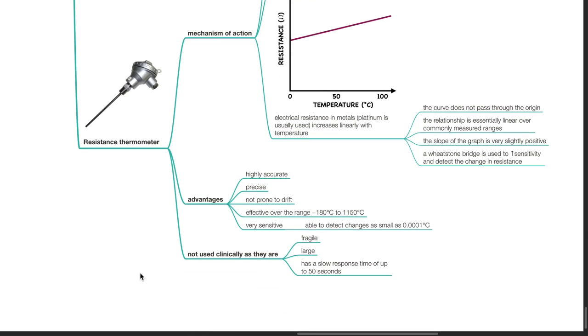Advantages of resistance thermometers: they are highly accurate, precise, not prone to drift, and effective over the range of negative 180 to 1,150 degrees Celsius. They are very sensitive and able to detect changes as small as 0.0001 degrees Celsius. However, resistance thermometers are not used clinically as they are fragile, large, and have a slow response time of up to 50 seconds.